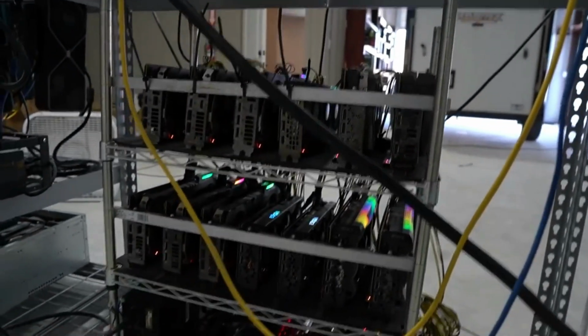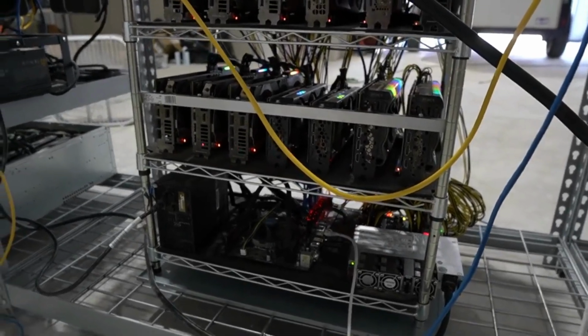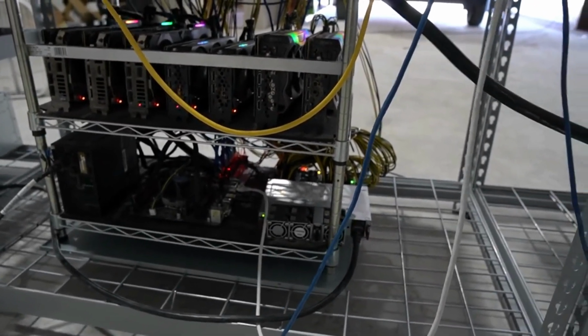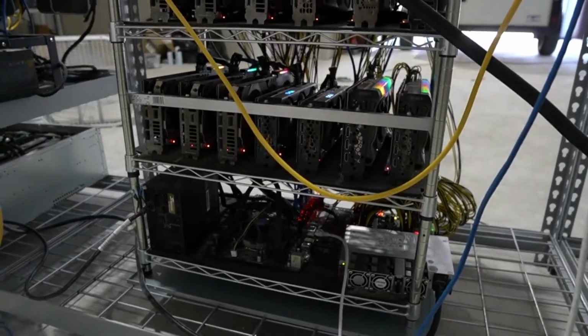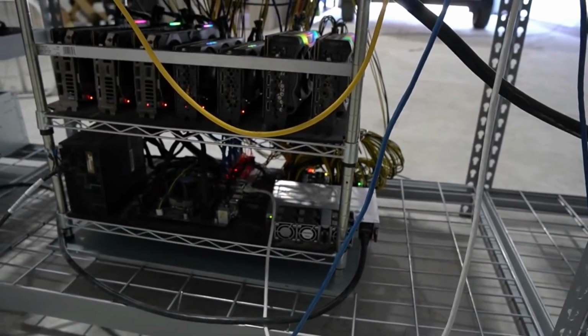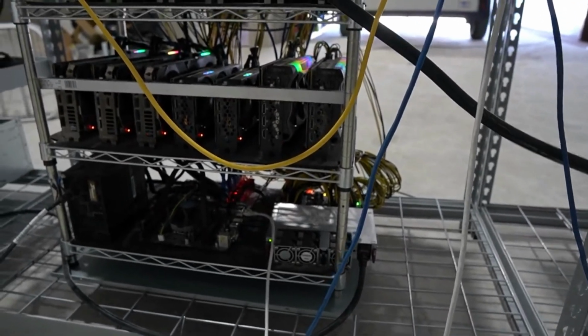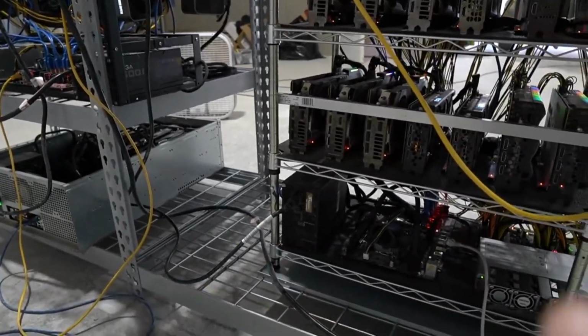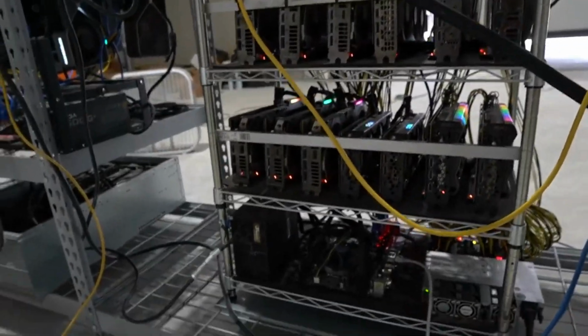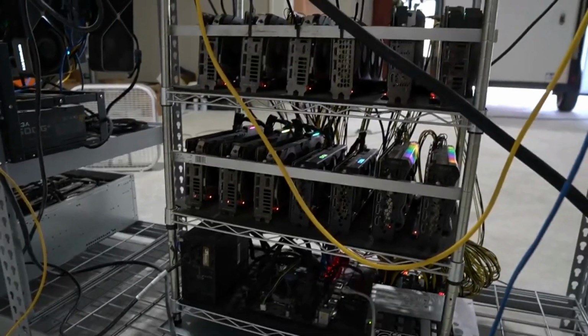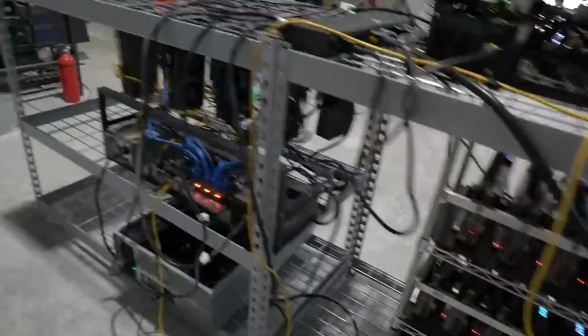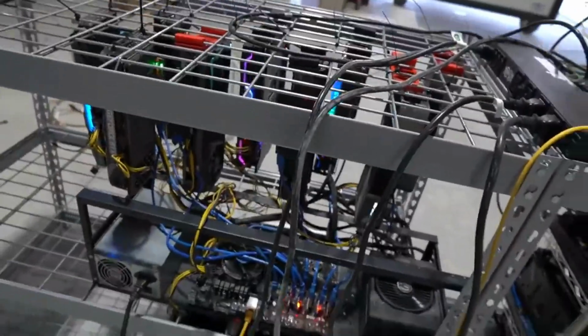You can take a look here where there's a ton of GPUs just sitting on different racks, and it's because it's a massive warehouse, people think it'll be fine. But in this case, this operation is actually having to shut down rigs because it's getting too hot in there. I don't know if he has any exit ventilation, but you need to start putting your GPUs in a location that funnels all the air out to the back, and you can put a hot cold dial.